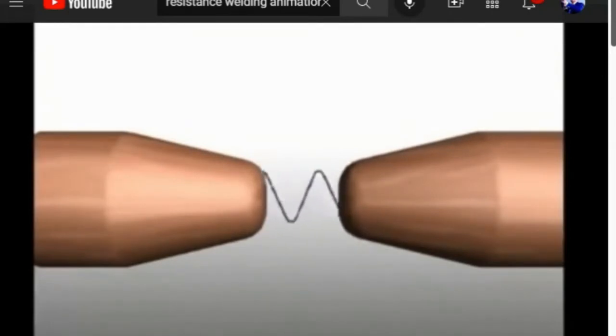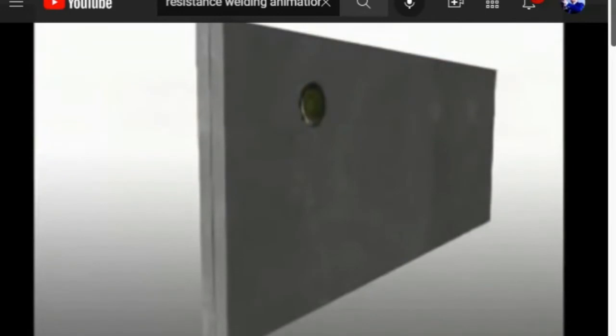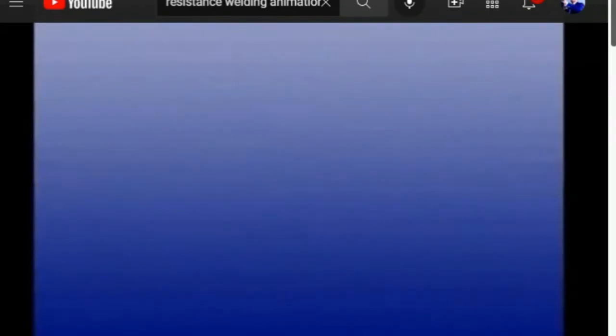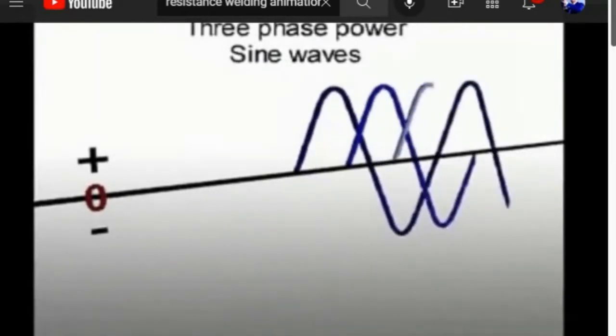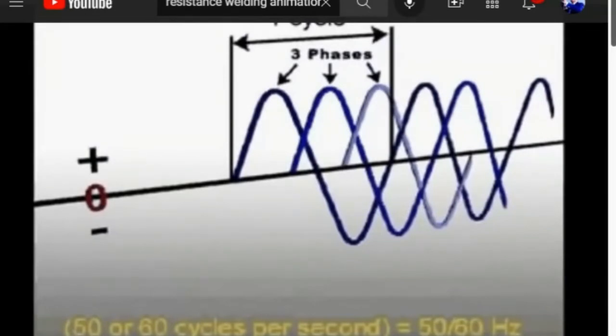When used with resistance spot welding, AC power quality negatively affects the weld quality due to irregular pulsating 60 hertz delivery of current. Three-phase power from the electric company provides better welder technology. The waveform starts as a single cycle, followed by a second sine wave delivered 120 degrees after the first, and a third sine wave 120 degrees after the second. AC current has one sine wave per cycle, but three-phase current has three sine waves per cycle, making three-phase current much better than single phase. However, three-phase sine waves still alternate through zero resulting in losses.